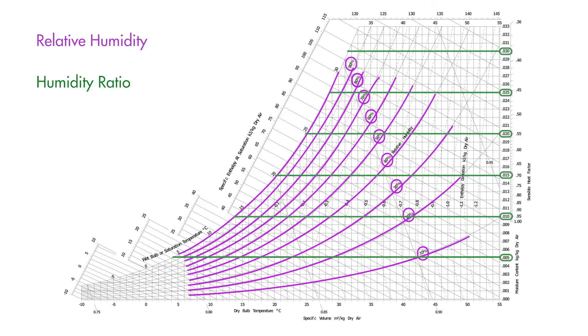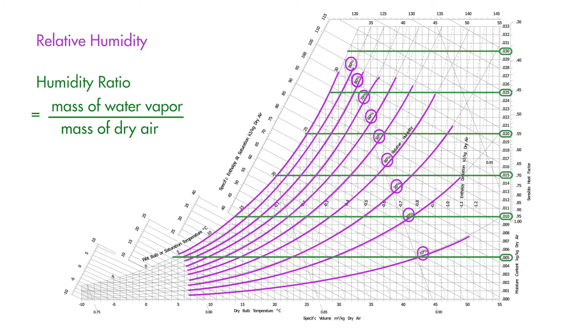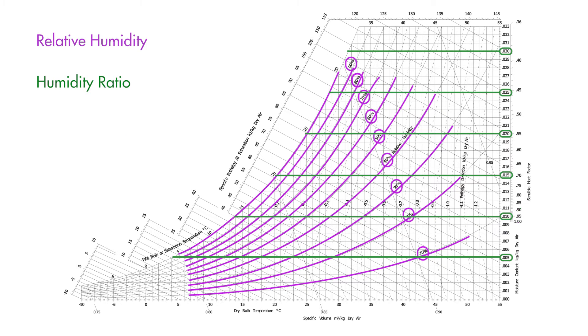And finally these green lines represent moisture content or humidity ratio. Humidity ratio is the ratio between the mass of the water vapour in the air to the mass of the dry air. So for example, a humidity ratio of 0.01 kg per kg dry air means that there is 10 grams of water vapour present in 1 kg of dry air. It is important to note that the warmer the air is, the more moisture it can hold, and hence why the relative humidity lines curve upwards.